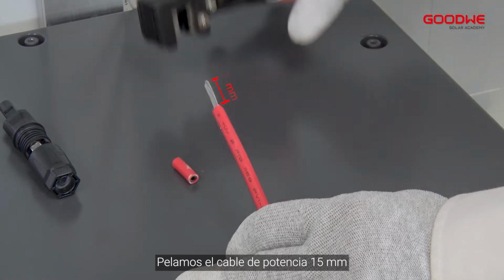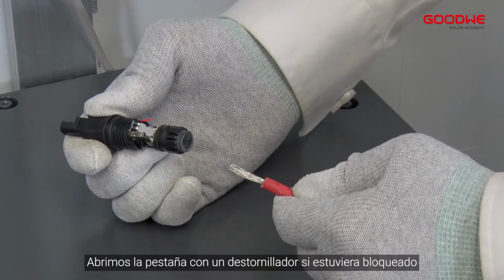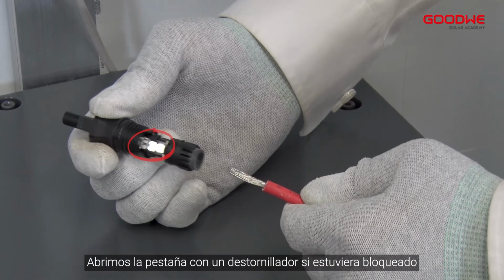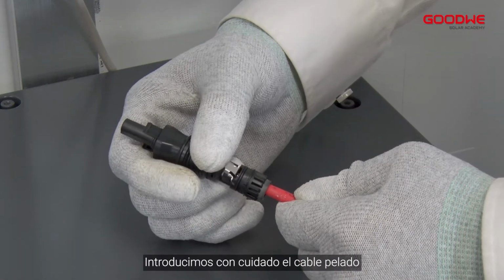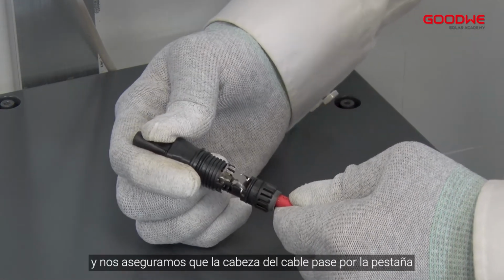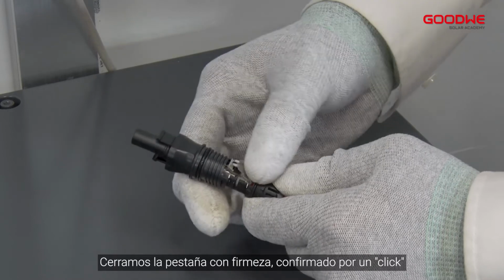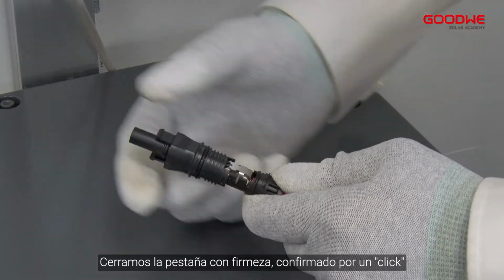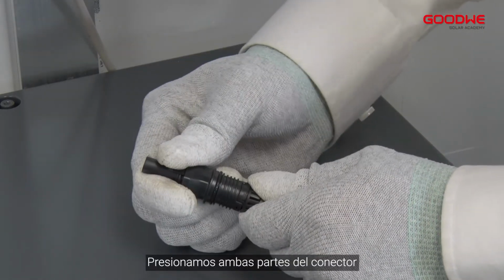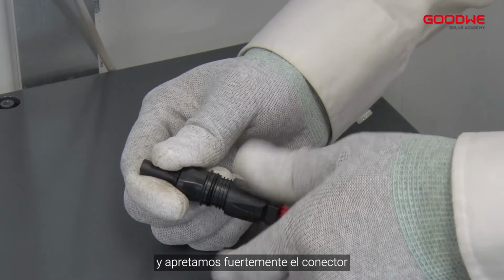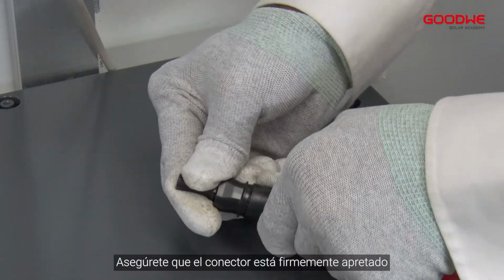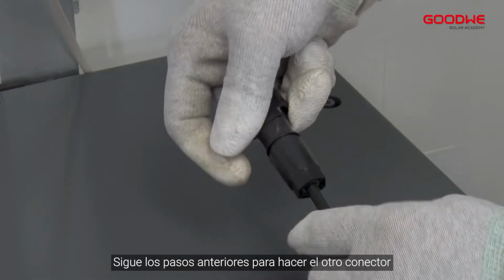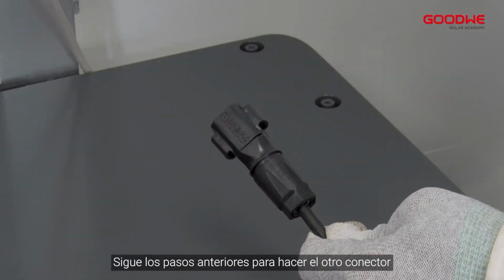Strip off the wire for 15 millimeters. Open the spring using a screwdriver if it's locked. Carefully insert the stripped wire, making sure the wire head is past the spring. Close the spring until you hear a click sound. Push the insert into the sleeve, and turn both sides to tighten the connector. Make sure the connector is tight enough. Follow the above steps to make another connector.